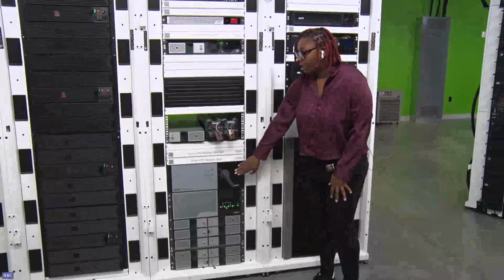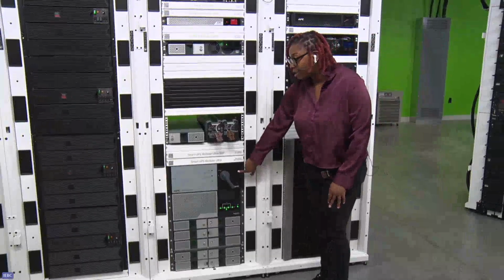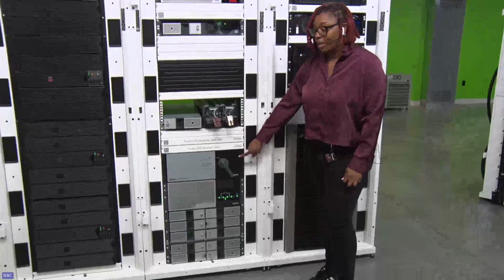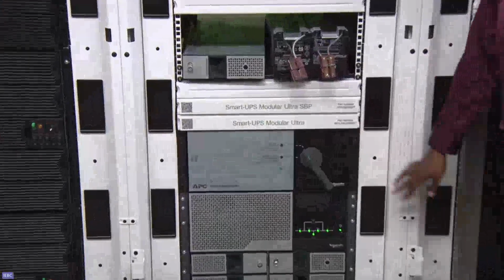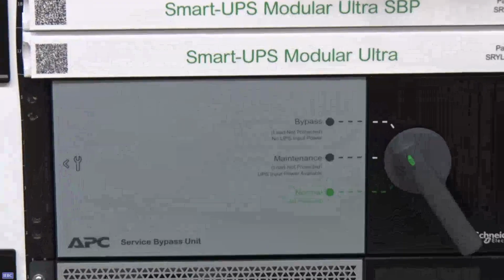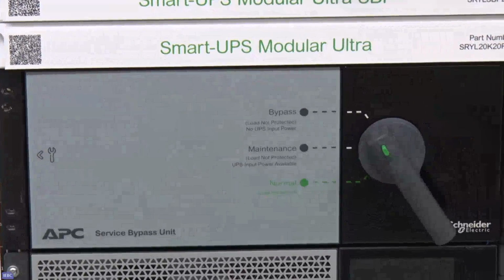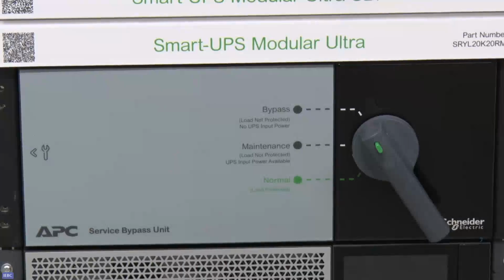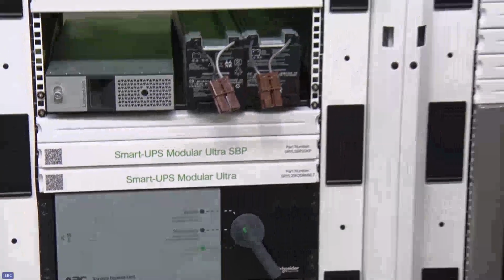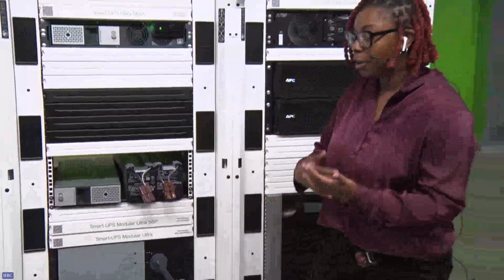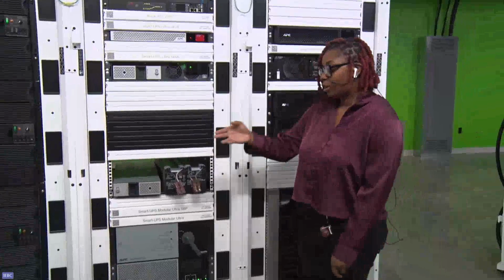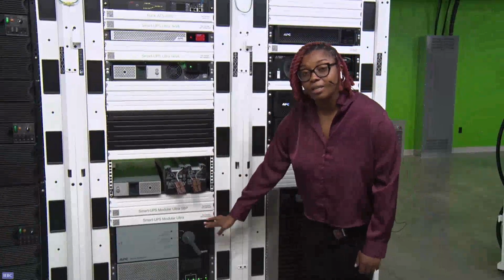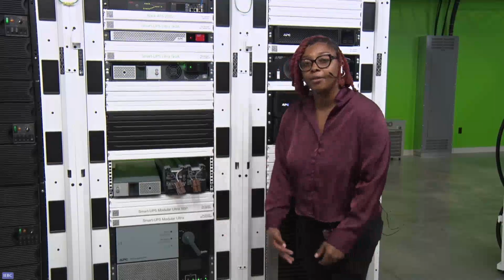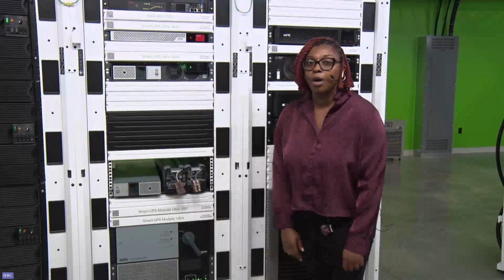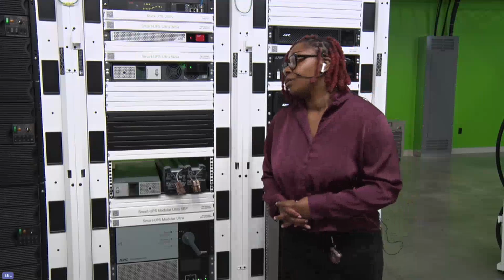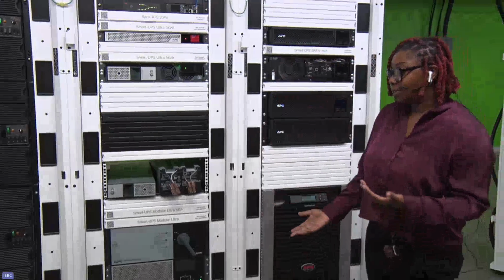This is also another optional piece to this UPS system, our service bypass unit. This comes into play when you need to completely gut out this UPS—you would simply put it in bypass, meaning the incoming AC power goes around your UPS system instead of through that double conversion. You can keep this energized, take out all your bad power modules and batteries, replace them, and then put it right back into normal operation when you're done. So this is really, really nice.